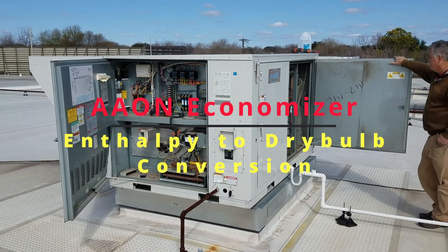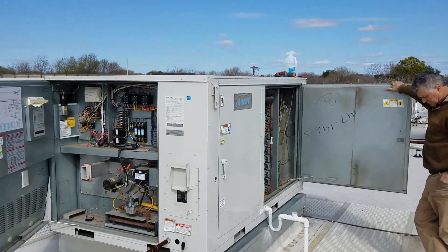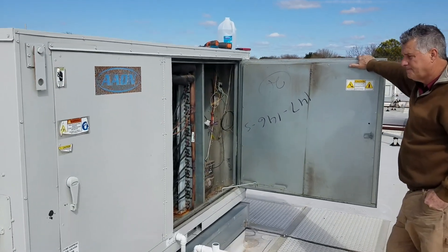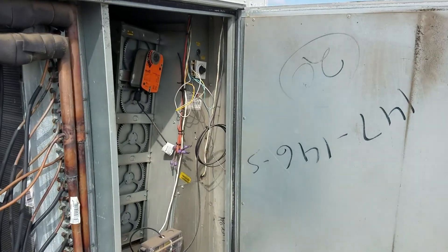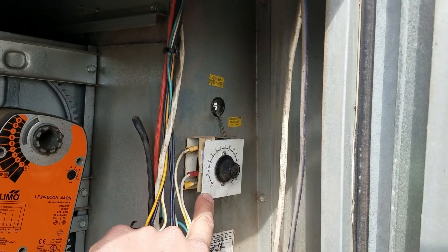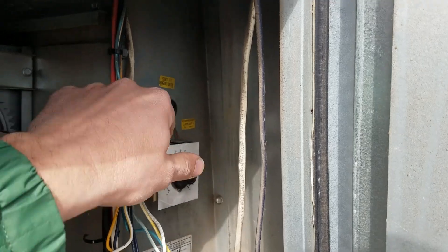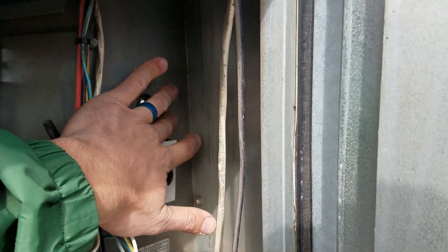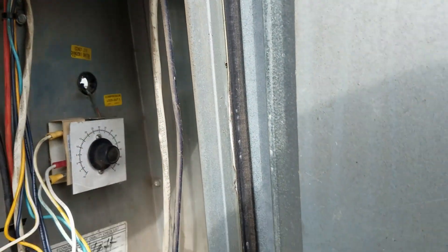Today we're working on these AAON units. They have an economizer that has a compressor lockout and an enthalpy changeover switch. The compressor lockout is a dry bulb with a refrigerant bulb run through a hole. Notes on the unit say 'economizer changeover switch compressor lockout.' The economizer changeover switch is enthalpy — we'll look at that now.